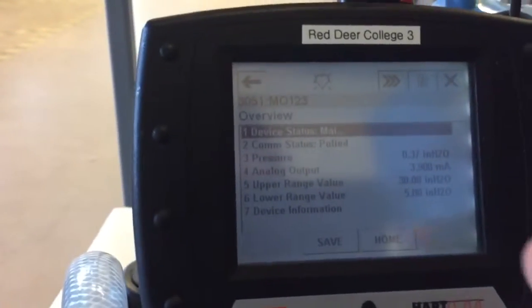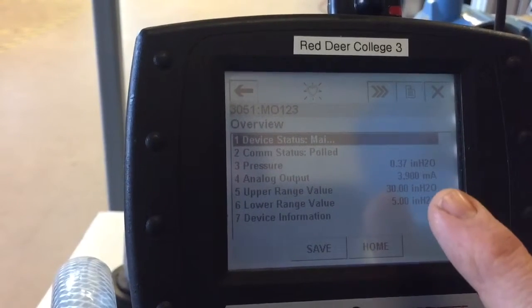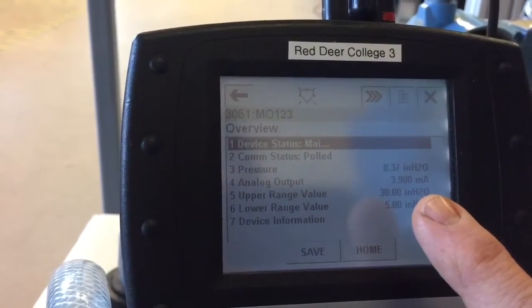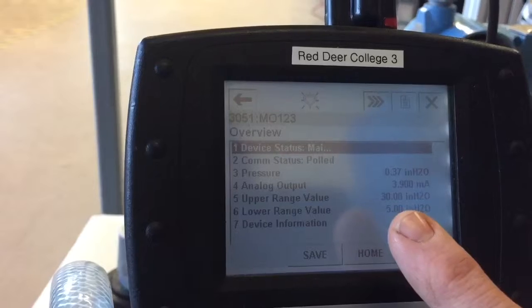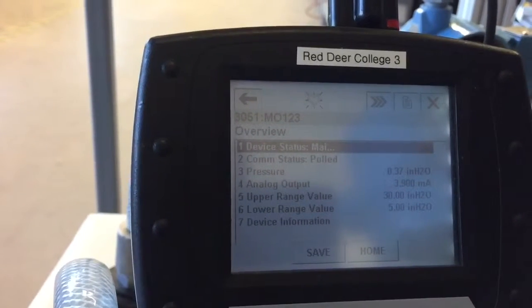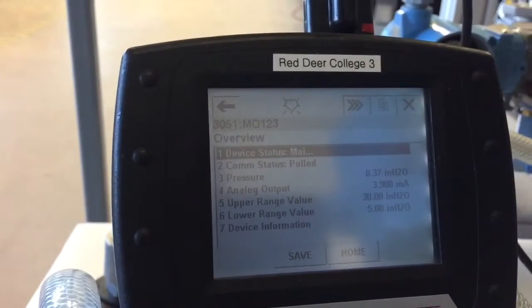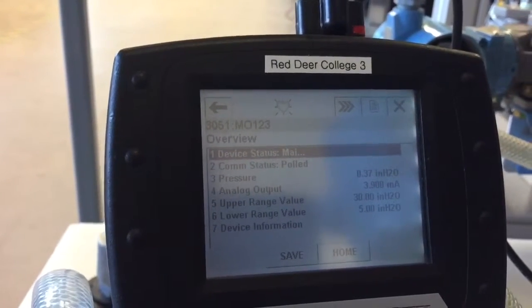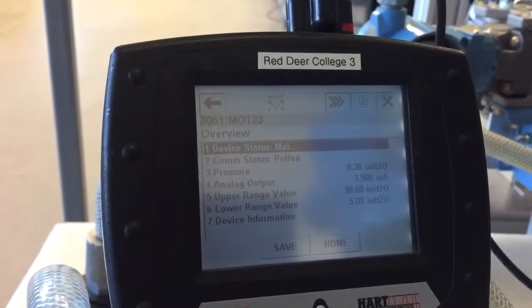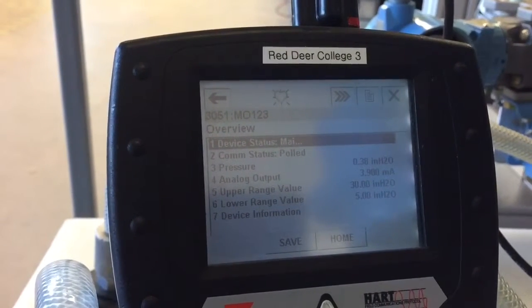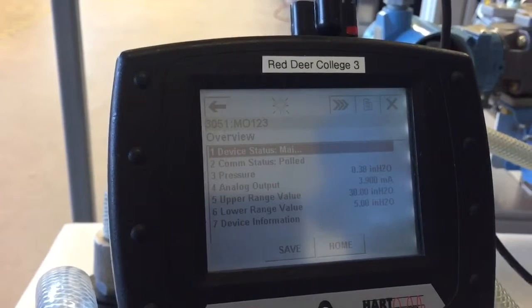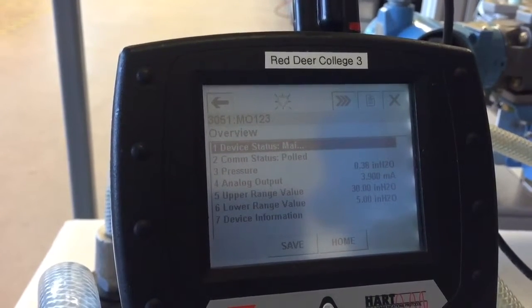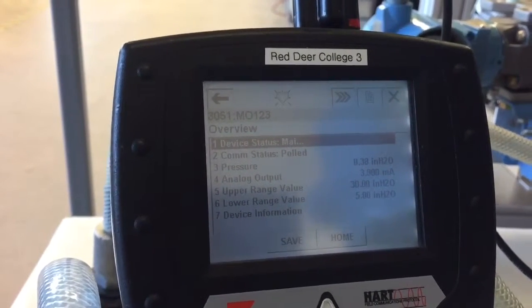So there, now you can see the units are in H2O, inches of water column, and our new range values of 5 to 30 inches. So the benefit of this is you don't have to have a technician going to all your devices connected to the DeltaV control system to rearrange them or change units. You can do it all right from the control system or from one workstation.